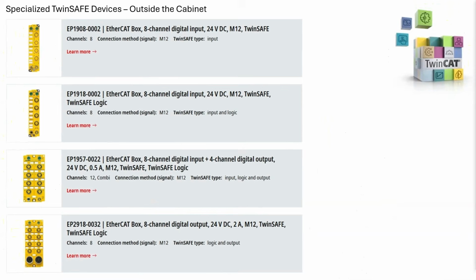Now that we have covered the DIN-mounted TwinSAFE terminals and the core safety logic components, let's shift our attention to Beckhoff's TwinSAFE EtherCAT box modules. These modules extend the TwinSAFE ecosystem directly into the field, giving you safety-rated I/O right at the machine, without the need for a control cabinet. These IP-rated TwinSAFE boxes are designed for harsh industrial environments where dust, moisture, vibration, and mechanical stress are part of daily operation. With their fully sealed housing and M8 and M12 connectors, they deliver safety functionality exactly where it's needed, while maintaining the same TwinSAFE workflow inside TwinCAT.